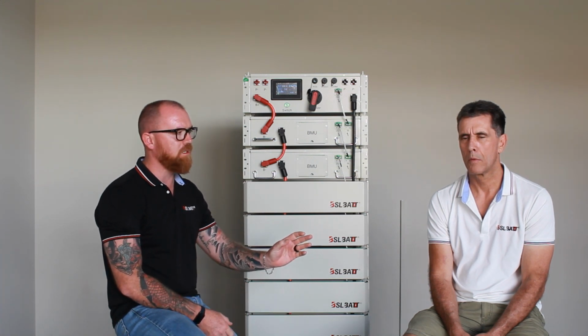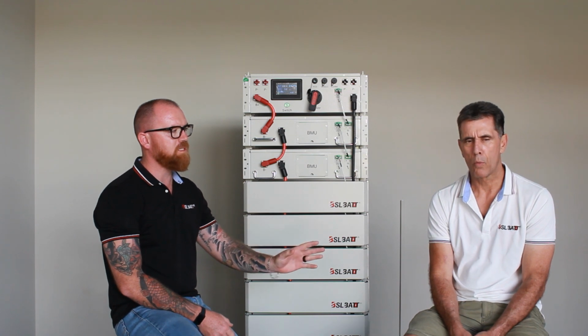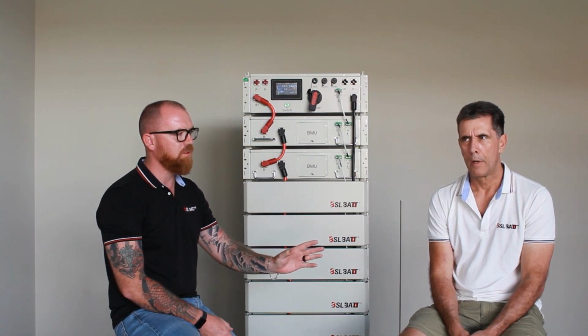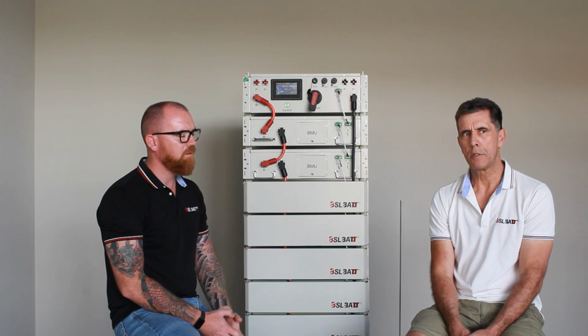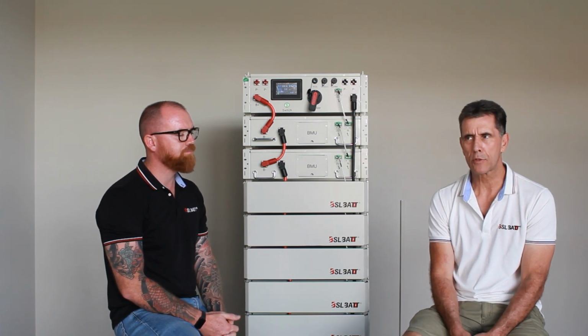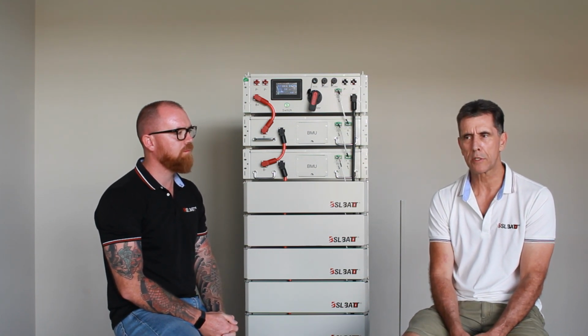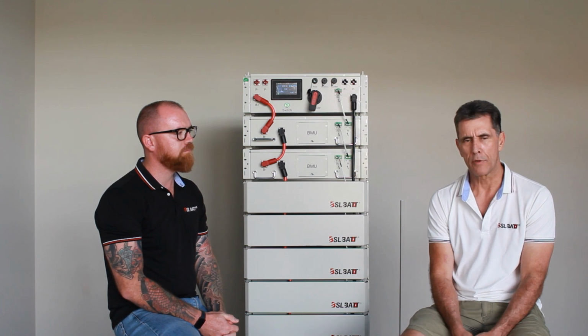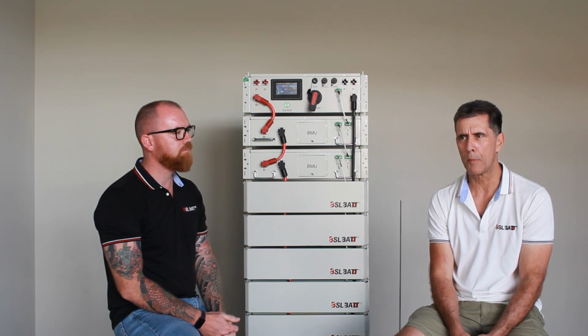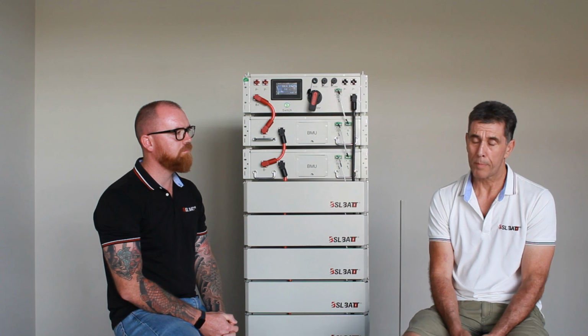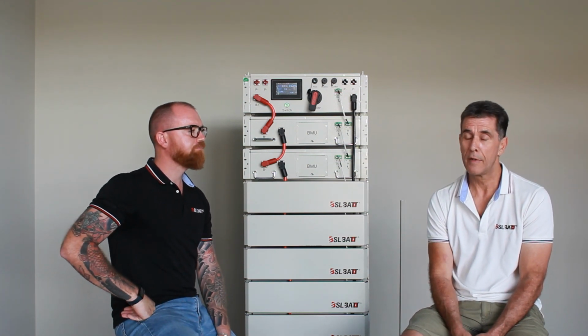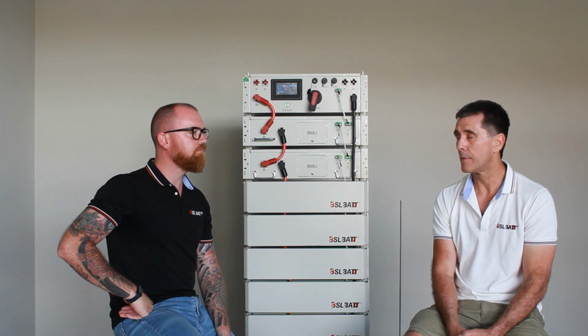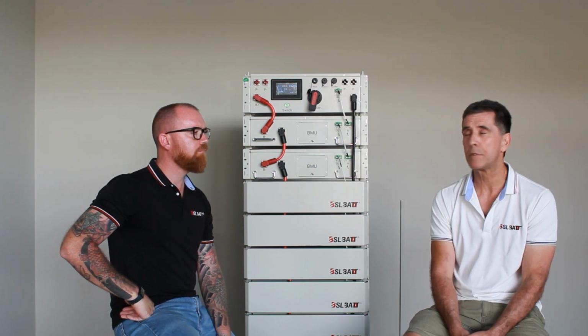Performance, 1C - why is that important? Most lithium cells should be able to give a 1C, controlled by the BMS. Our batteries are 1C, meaning we can give 135 amps times the nominal volt. That's quite a lot of power. So if you've got 500 volts times 135, that's quite a lot of wattage you can pull out of these batteries.